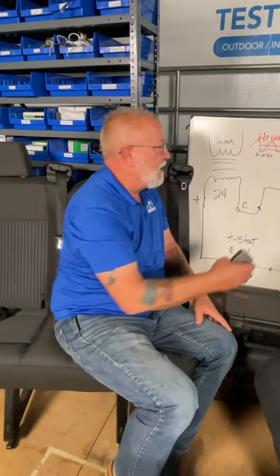Now this is something we're going to run into more and more as we get away from the standard, basically old style thermostats that were just switches, and we get over now to more data carrying thermostats, because now the noise becomes interpreted as something to the control when it's not. You're reading noise. So one of the things that we recommend, and the manufacturers recommend, if you read the instructions, when you have a communication error, first try this: turn the power off. So you shut the power off to the air handler, you shut the power off to the condensing unit, wait for the thermostat to go blank, and then reestablish power. Some of them want the condensing unit on first and then the air handler or furnace second. Some of them want it the other way around. Regardless, what happens when you shut the power off is you've stopped this.